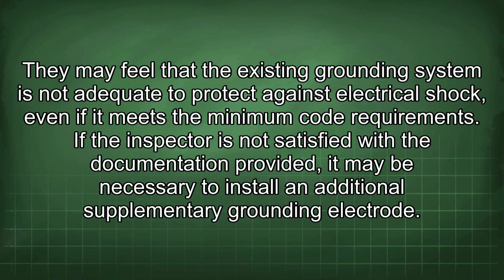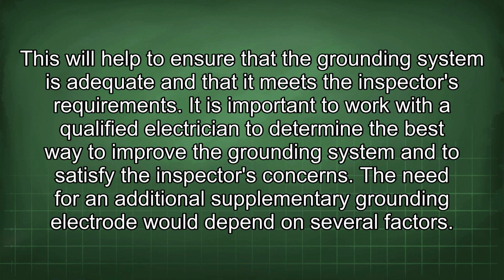the minimum code requirements. If the inspector is not satisfied with the documentation provided, it may be necessary to install an additional supplementary grounding electrode. This will help to ensure that the grounding system is adequate and that it meets the inspector's requirements. It is important to work with a qualified electrician to determine the best way to improve the grounding system and to satisfy the inspector's concerns.